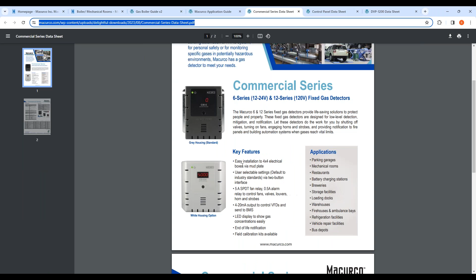That's going to be UL 2075, both CO and NO2. I emphasize that because there are no sensors out in the market right now that have the NO2 UL 2075 listing, because you can't list it to UL 2075 if the sensor isn't rated above 3 years. There is a manufacturer that found a sensor model that works for 4 to 5 years.